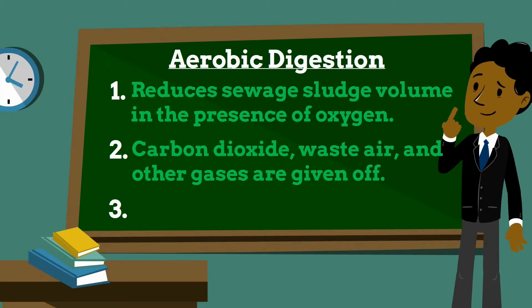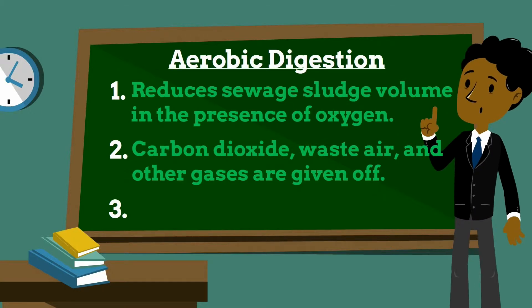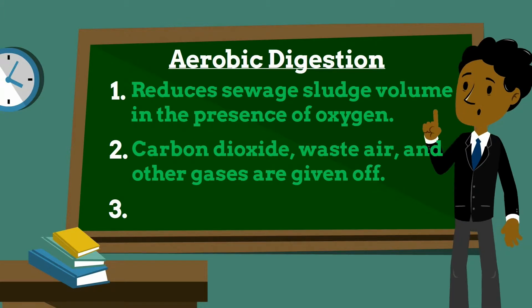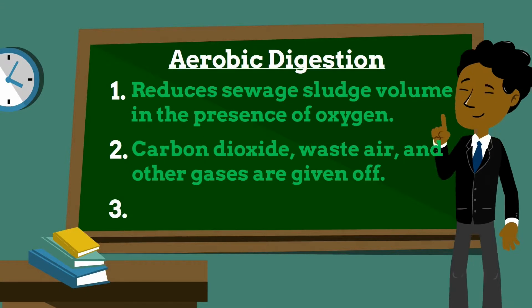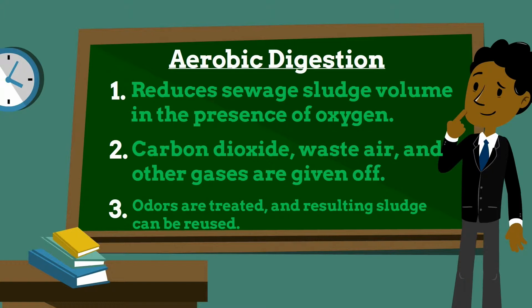Carbon dioxide, waste air, and small quantities of other gases including hydrogen sulfide are given off. Bacteria rapidly consume organic matter and convert it into carbon dioxide, water, and a range of lower molecular weight organic compounds. As there is no new supply of organic matter from sewage, the activated sludge biota begin to die and are used as food by other bacteria. These waste gases require treatment to reduce odors in treatment facilities close to housing or capable of generating public nuisance.